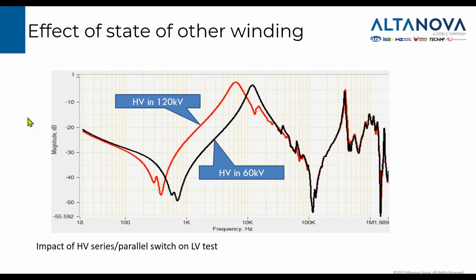Another effect of state of the other winding of the transformer. Here is example of a transformer which has high voltage winding configurable. So it can be either set in 120 kilovolts connection, meaning two half coils are connected in series, or if they are connected in parallel, high voltage winding will have 60 kilovolts. So obviously they are mechanically in the same position, but there is a switch allowing that. And depending on which position that switch is in, low voltage winding again gives us different measurements.